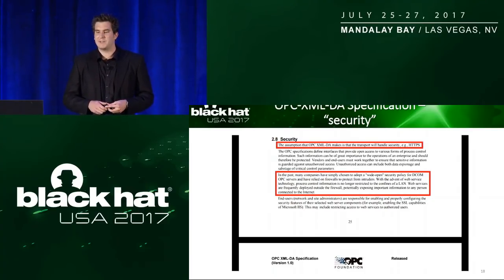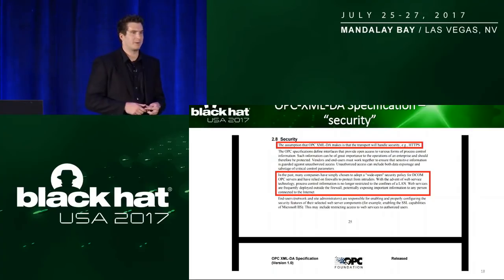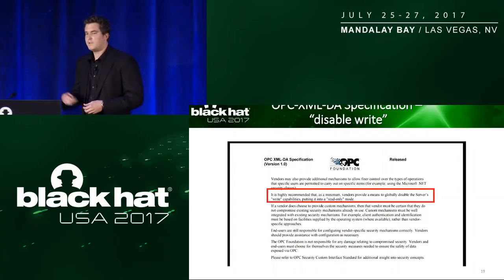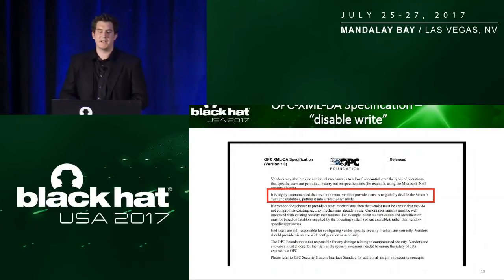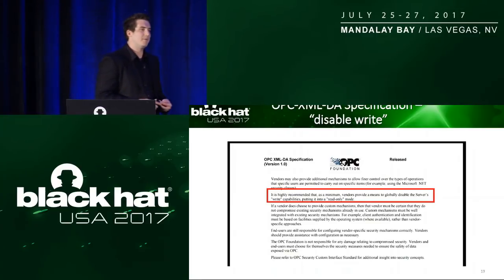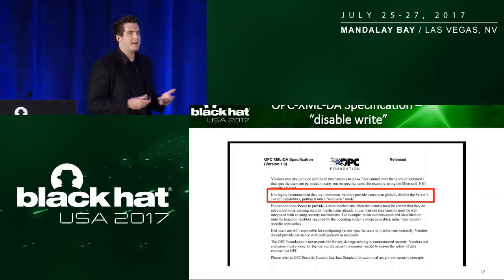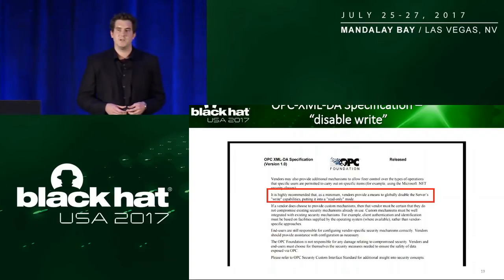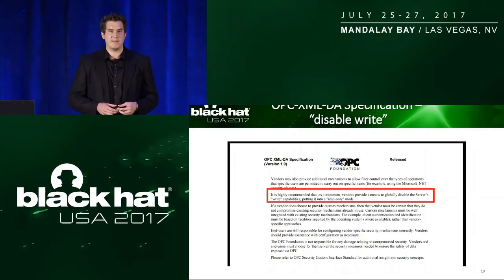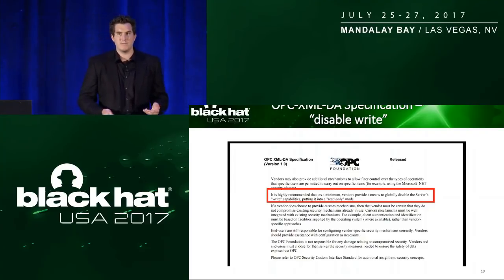In every case we looked at that was using this protocol for command and control, no one's doing this. No one's encrypting these messages or these protocols. If you look further in the spec, it also recommends disabling the ability for just anybody to send these arbitrary write message requests to the OPC server, having some sort of authentication mechanism, or putting the OPC server into read-only mode.